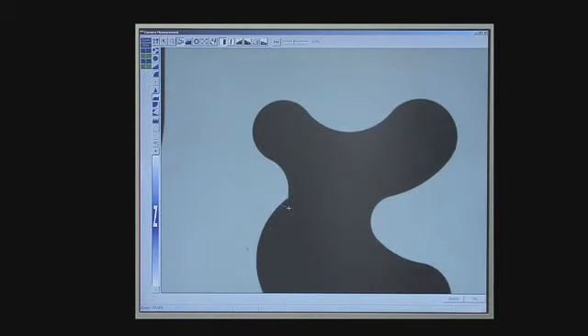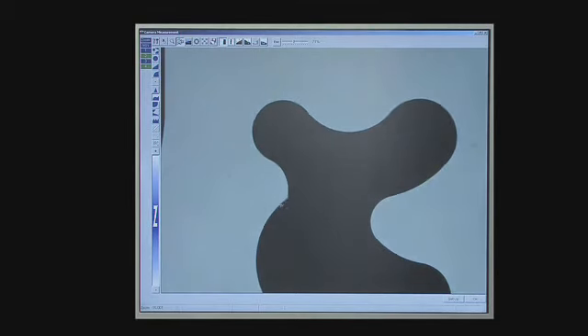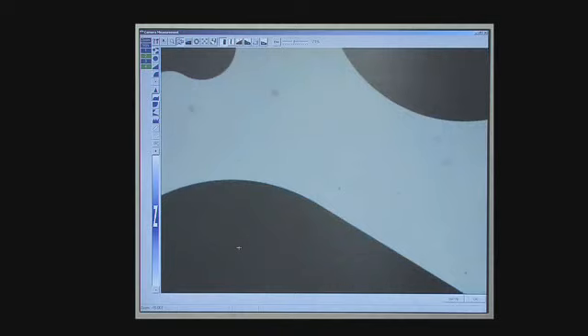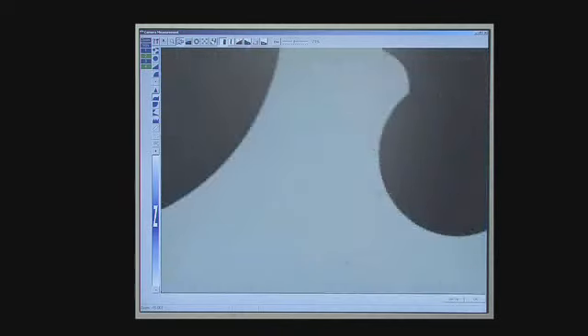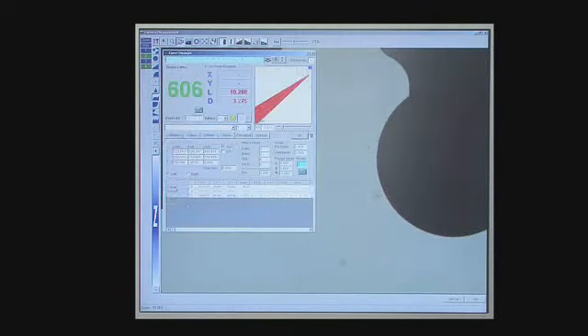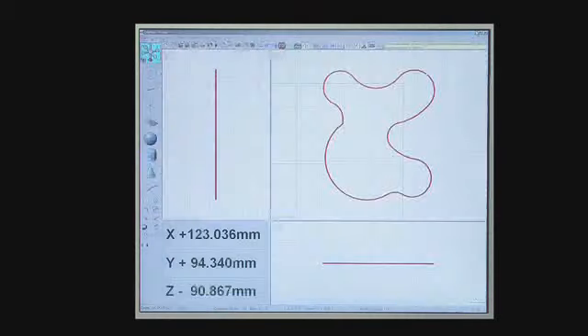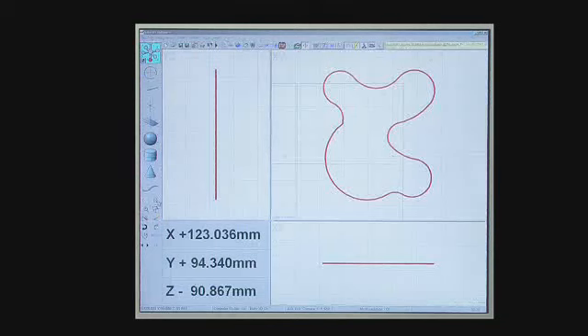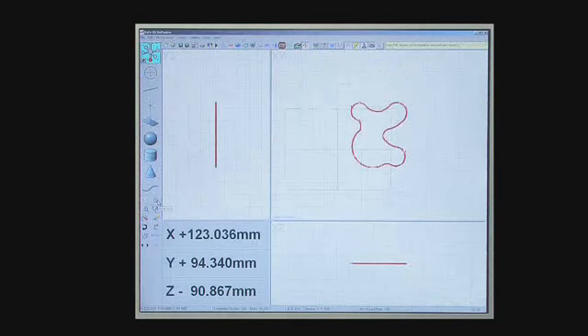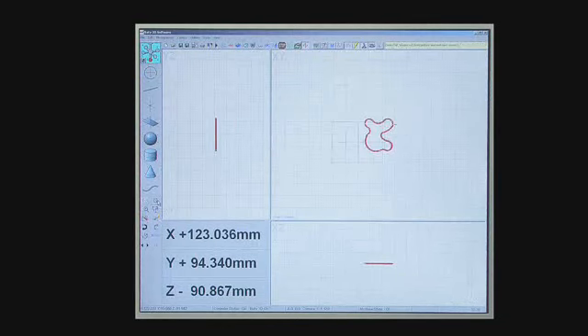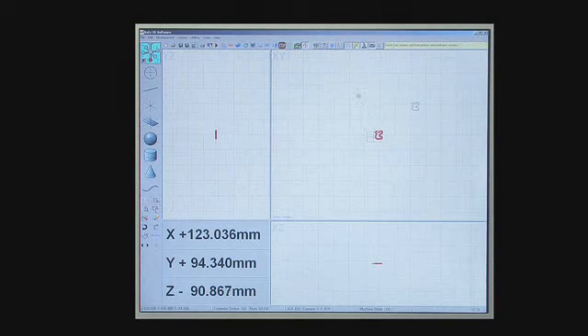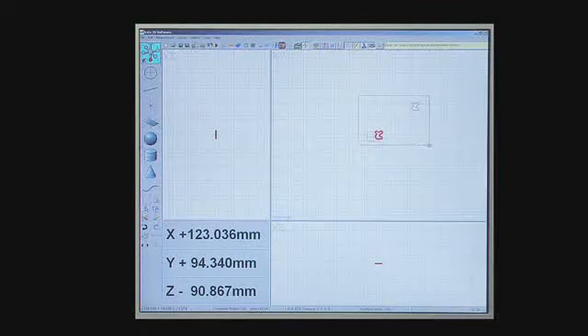A scanning tool is also available to automatically capture data from a free-form profile shape. This data can be best fitted to an imported DXF master profile to determine profile error.